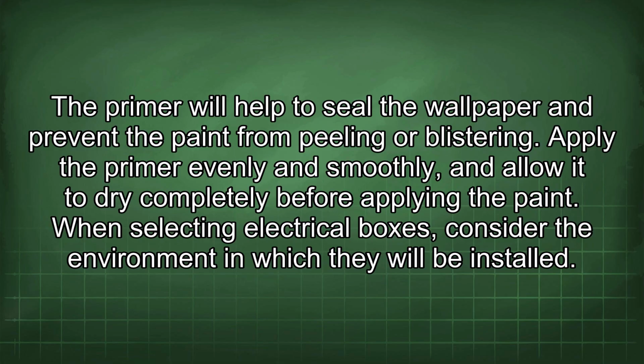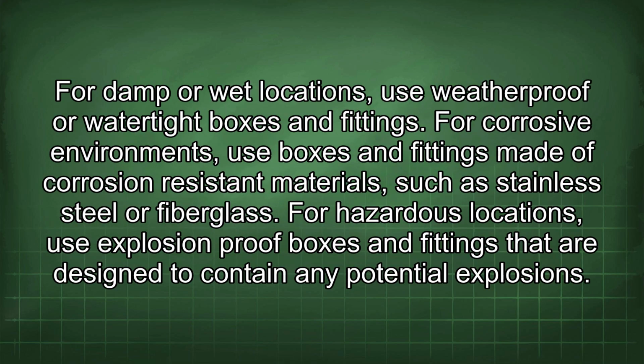When selecting electrical boxes, consider the environment in which they will be installed. For damp or wet locations, use weatherproof or watertight boxes and fittings. For corrosive environments, use boxes and fittings made of corrosion-resistant materials such as stainless steel or fiberglass. For hazardous locations, use explosion-proof boxes and fittings that are designed to contain any potential explosions.